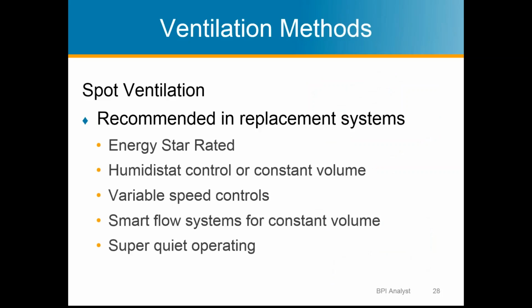And then in spot ventilation, and this is what we see, this is bathroom fans and kitchen exhaust hoods. What you want in them, ideally, you're going to have an Energy Star rated fan with a humidistat control. And a humidistat is a moisture sensor, so if you had spot ventilation in your bathroom, it would automatically turn itself on and off according to the level of humidity in the room. Variable speed is also a good option.